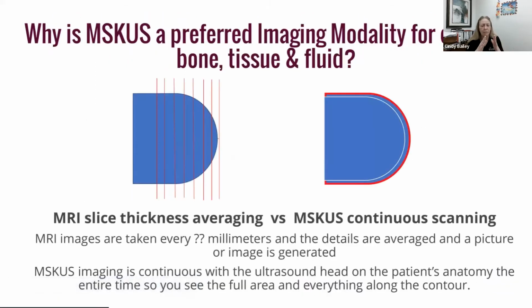The other comparison that we make between ultrasound and MRI is that an MRI machine takes slices. They usually take slices every 4 millimeters, but it depends on the machine and whether it's a research machine or not. So with an MRI, we take slices every 4 millimeters, then take what's on those images and average it, and then we make these beautiful images for you. But those images don't see anything in between the 4 millimeters. So you have 3 millimeters worth of stuff that the MRI machine did not image. It's just averaging those 4 millimeter slices, and that's what gives you the image.